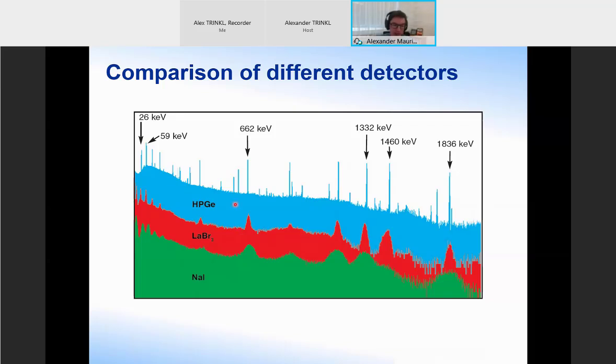And here you can really see that on the high purity germanium detector spectrum, you can see a lot of peaks, some of which are close to each other, which on the worse resolution detectors get joined together and swallowed up by other peaks next to them, and you basically lose a lot of information about the individual peaks. And on the sodium iodide, you only see really a few peaks in the end in the spectrum, where in the germanium detector you saw several dozen peaks. So this is part of the reason why we generally go for the high purity germanium detector for the precise measurements by gamma ray spectrometry.